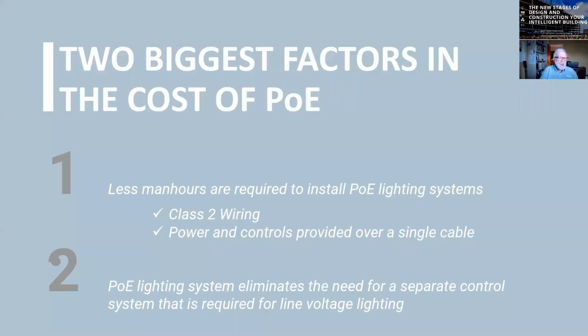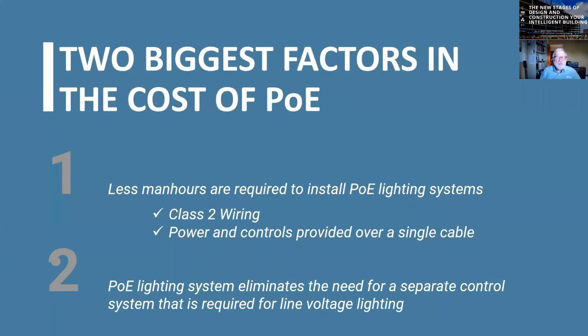There are two factors in the cost of PoE that make it attractive. Number one is less man hours required to install the PoE lighting systems. It's class two wiring, which means it does not have to be in conduit. The power and controls are provided over a single cable, so I don't have power run to the light fixture and a separate low voltage control circuit. The savings really is in the man hours.